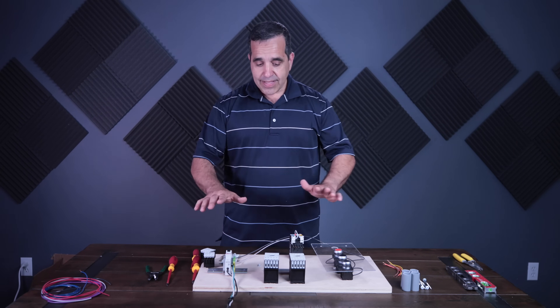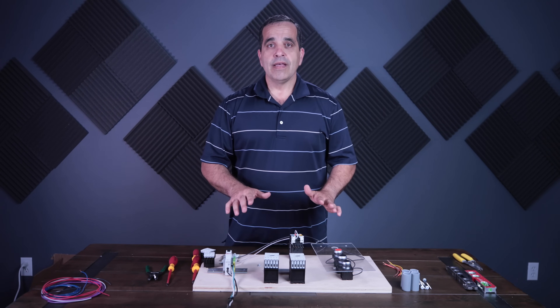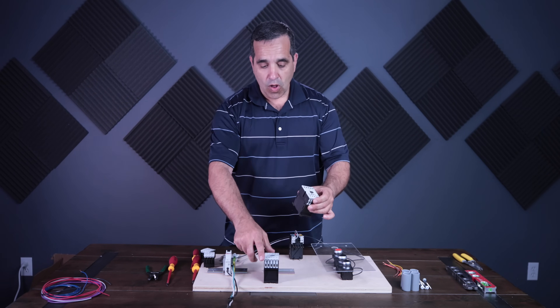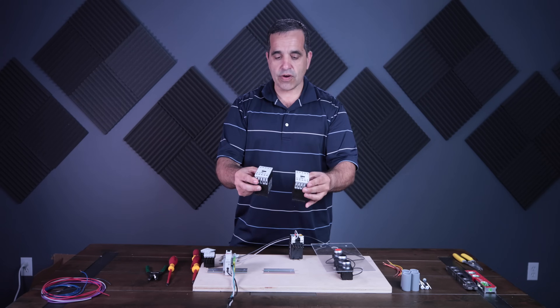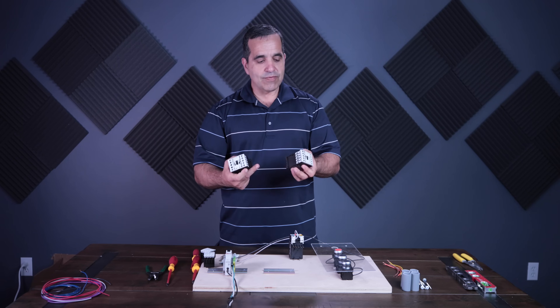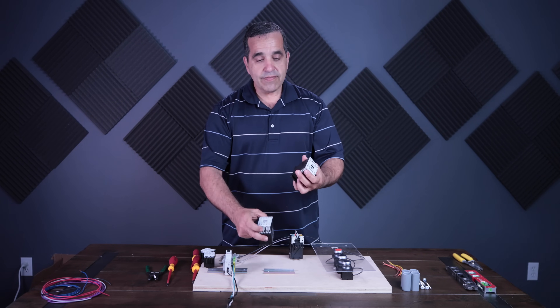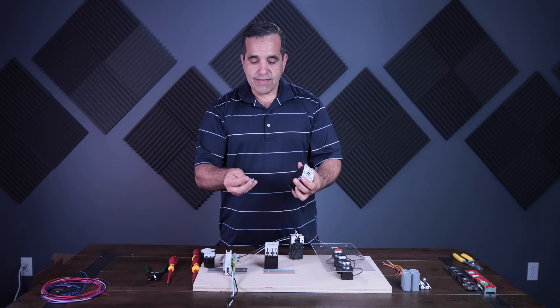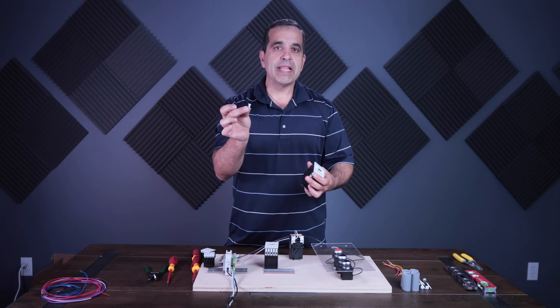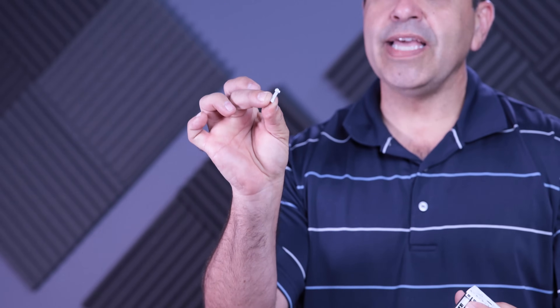So how do you wire these up properly to avoid that situation? First of all, before I get started wiring this up, I want to show you — on a starter, all I have is two starters. These are Eaton IEC style starters. I have two of them; they are individual starters. Now this little product right here, this small piece of plastic, is a mechanical interlock.